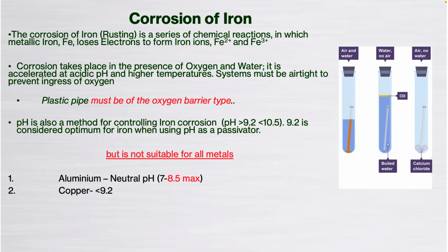You can use pH, so alkaline pH is a way of controlling corrosion. So long as you don't have aluminum, you could actually operate pH anywhere between sort of 9.2, which is perfect, but certainly sub 10.5. And managing just pH alone will assist with controlling corrosion to some degree. But it's not suitable for all metals, as I say. For aluminum, anything over 8.5, and you're going to start to cause corrosion, and you're going to start causing problems really for any boilers if they are aluminum.